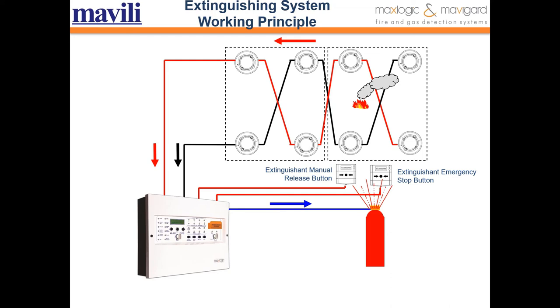As you can see in the animation, if fire is detected in this area — there are four detectors for this area — and all detectors are in fire alarm, then as you know both the black line and the red line are in fire alarm, and the extinguishing process starts. If only the red line is sending a signal, that will not start the extinguishing process.